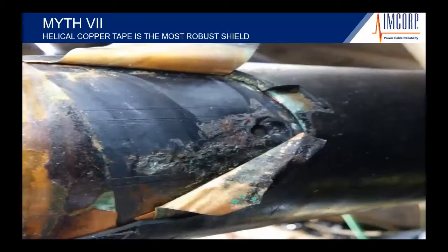Somehow, in a contaminated area or environment, moisture ingress can get into the termination. When it gets into or in between the overlapping of the copper tape shield, it can corrode that copper tape shield. By doing that, it interrupts the electrical contact between the overlapping layers. It forces a high-frequency signal to propagate helically versus longitudinally or axially throughout the cable. So it causes a pitting type of action when it sees higher voltages. If this was just at 50, 60 hertz, probably wouldn't be a real big problem. But when it sees these transient voltages, it begins to pit out the semiconductor material. And in this case, a little extreme, it starts to break down the insulation of that cable.